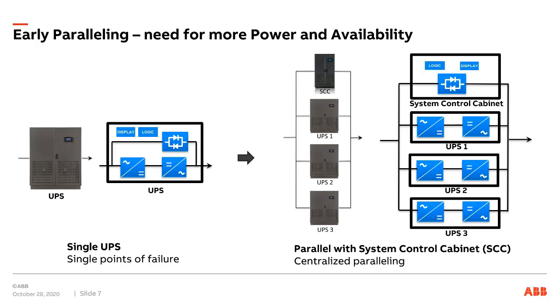And what has driven the development of different configurations and the features and specifications for UPSs is that we learned, that was before my time. I'd been in the business for a while, but not all the way back then. Very, very rapidly, like the good old truth, anything man-made will fail. Which means that now we put a UPS in the line between the utility and the critical load, but that single UPS is also a single point of failure.